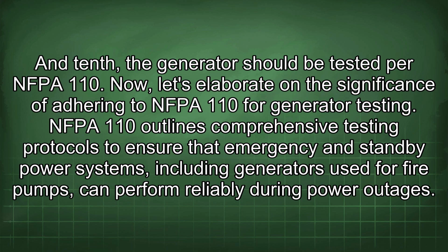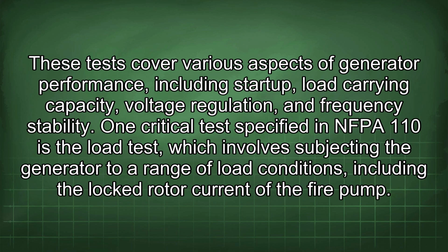Now let's elaborate on the significance of adhering to NFPA 110 for generator testing. NFPA 110 outlines comprehensive testing protocols to ensure that emergency and standby power systems, including generators used for fire pumps, can perform reliably during power outages. These tests cover various aspects of generator performance, including startup, load carrying capacity, voltage regulation, and frequency stability.